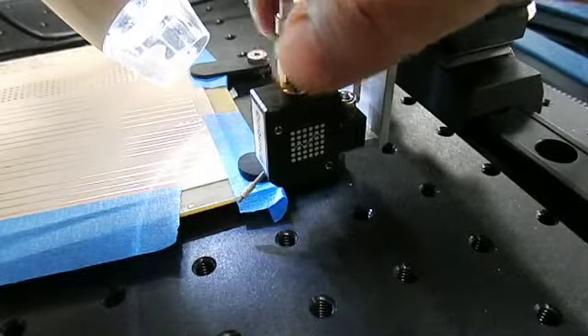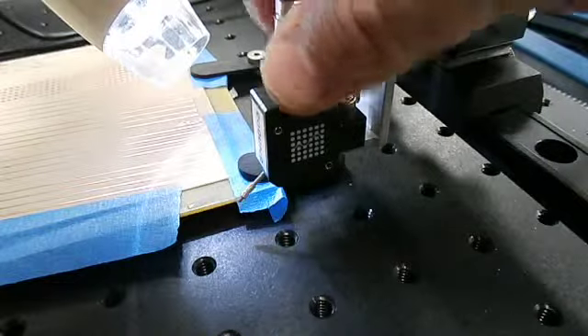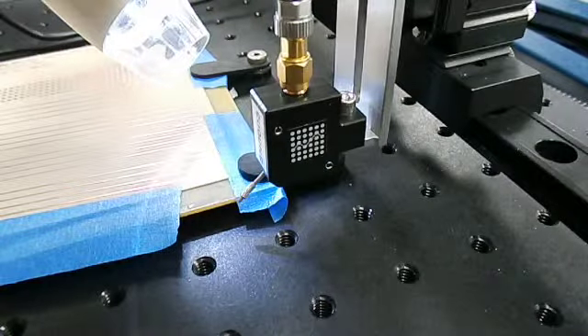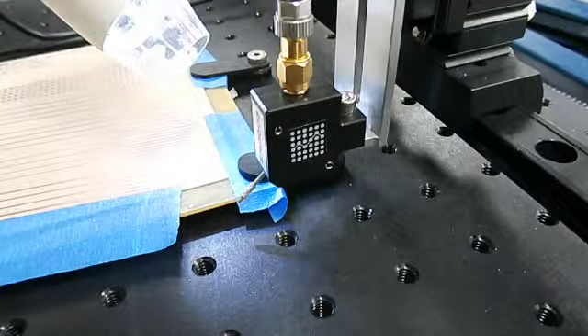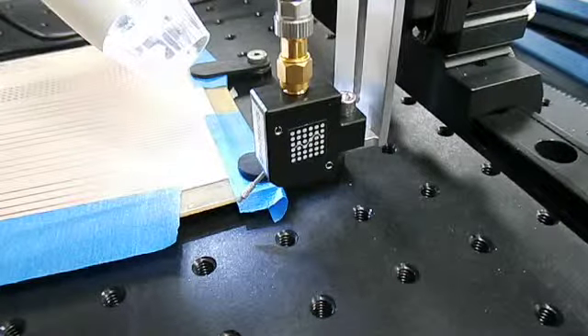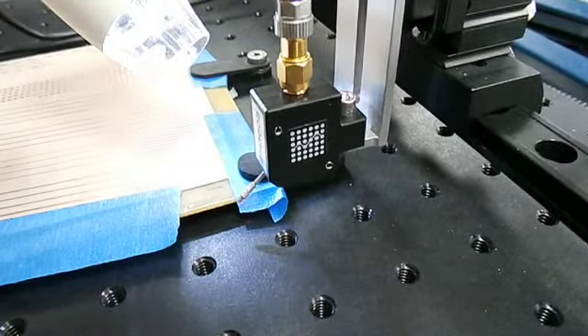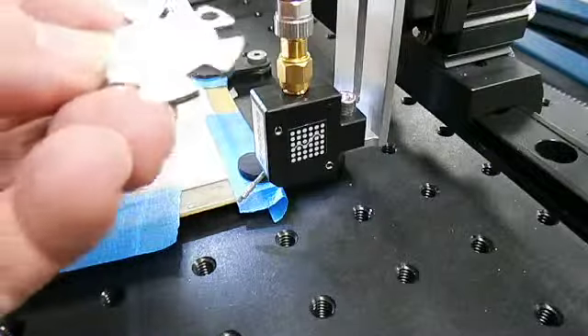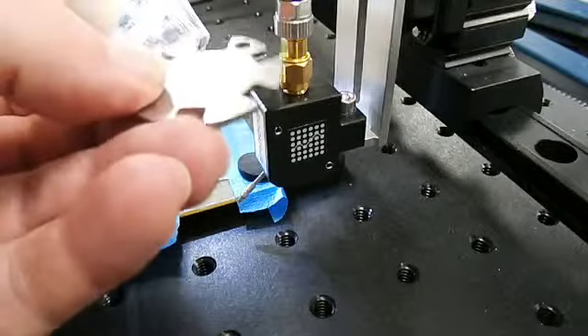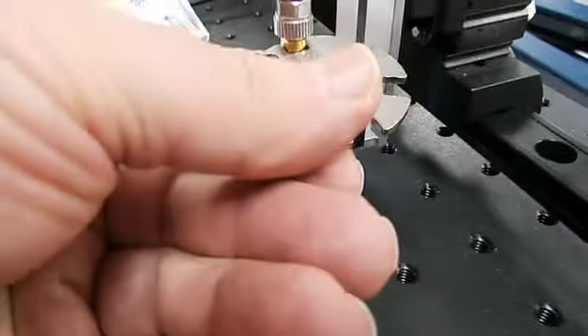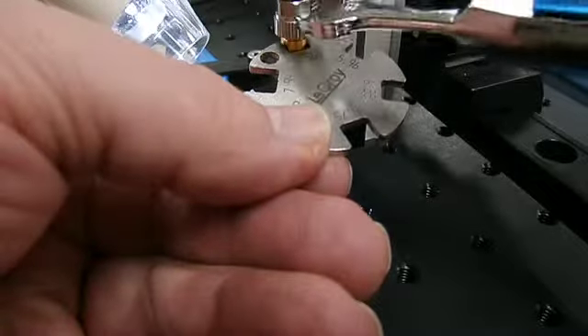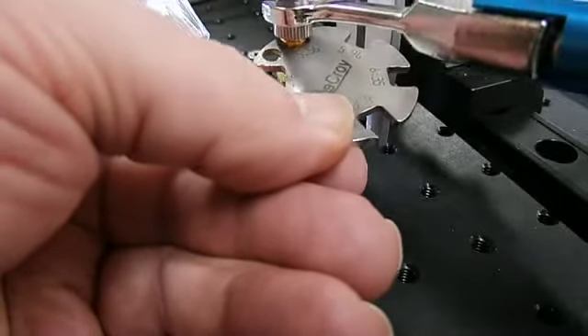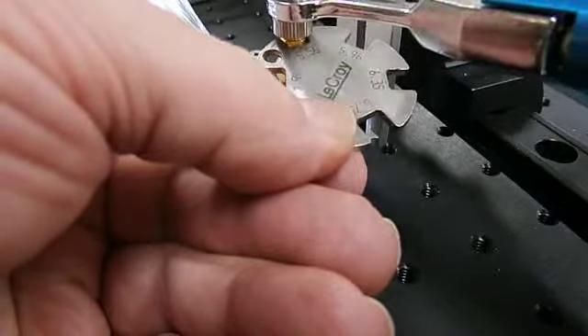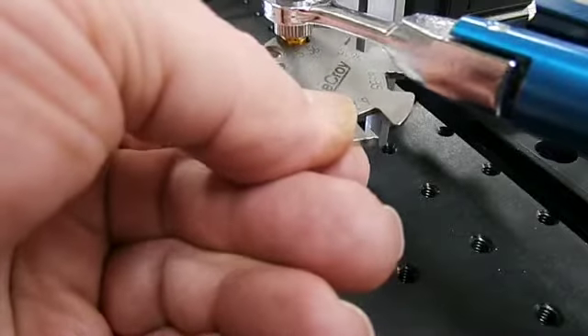I'm going to finger tighten, in this case a 2.92 millimeter cable to the top of the probe, and then I'm going to use two wrenches. One wrench is going to hold on to the body of the gold connector at the top of the FP12, and I'm going to use a second wrench that came with the network analyzer I'm using to tighten the cable to the prescribed torque for the 2.92 millimeter connector.